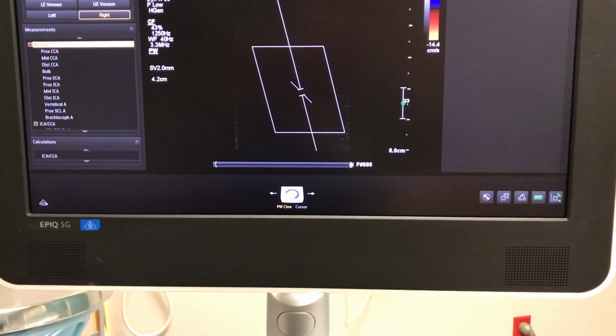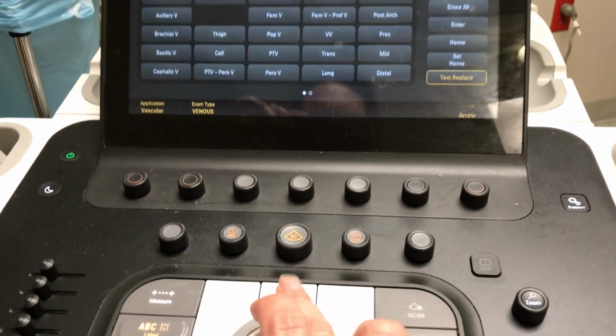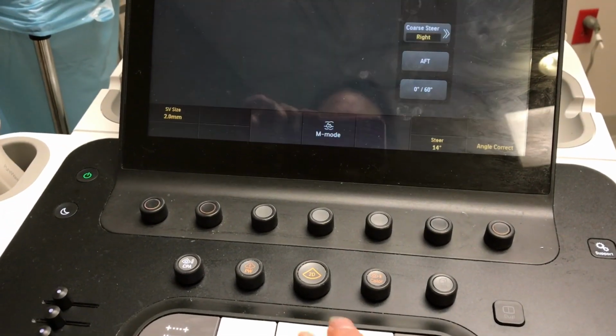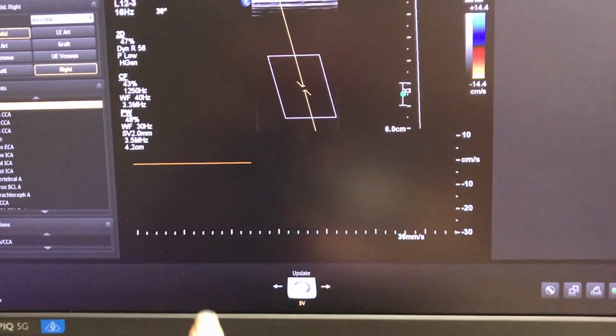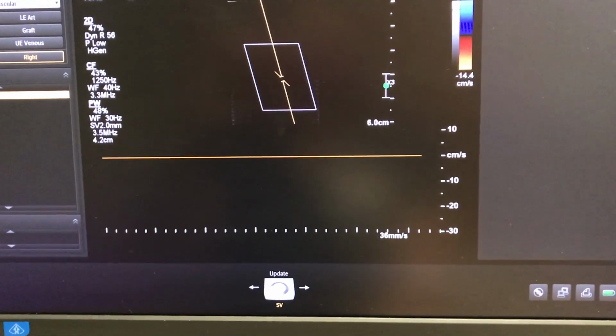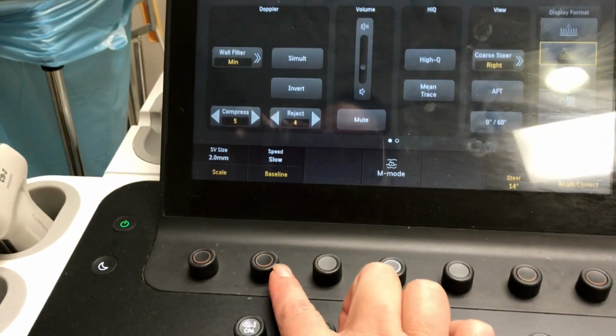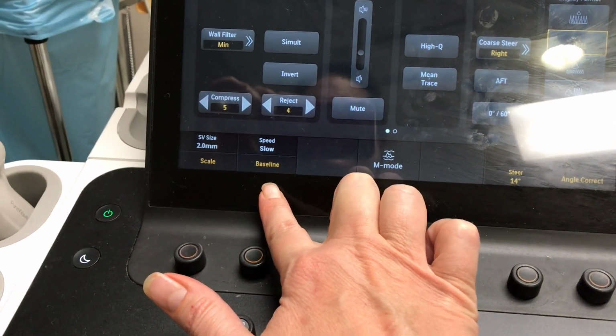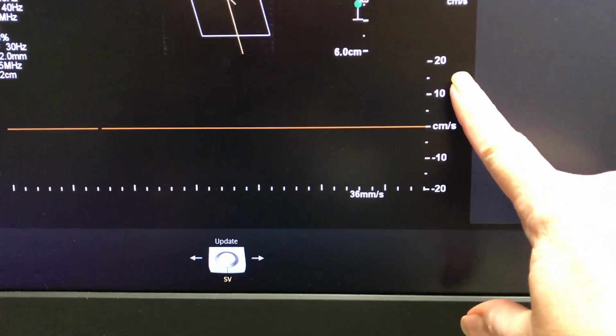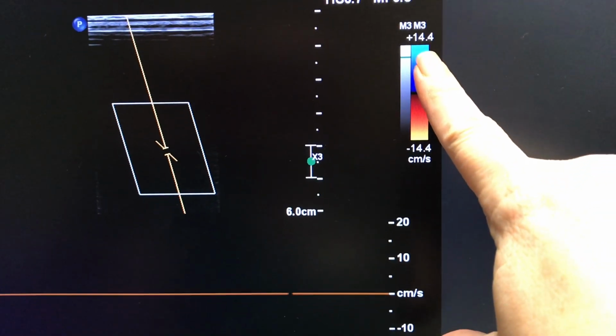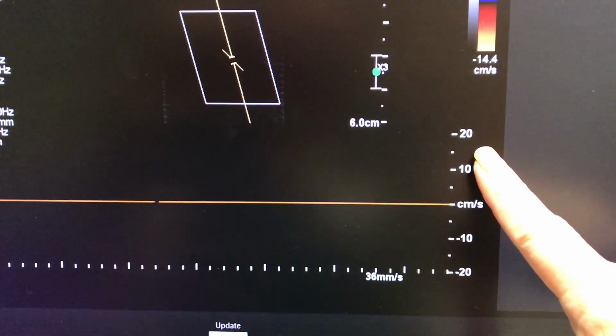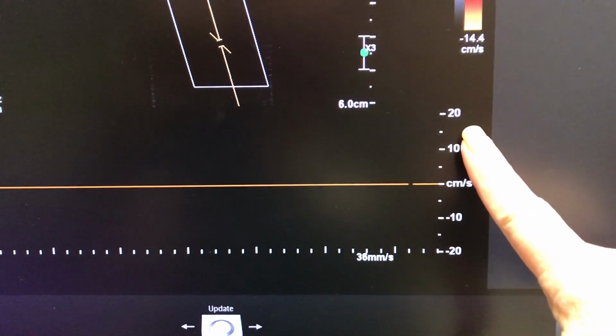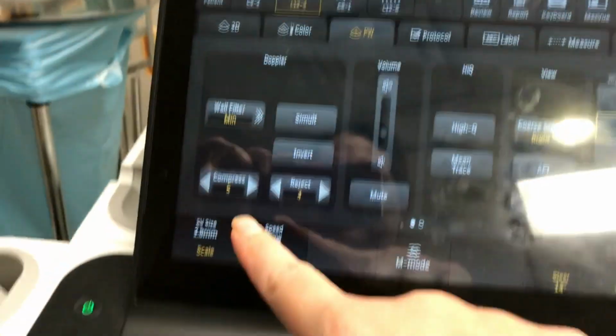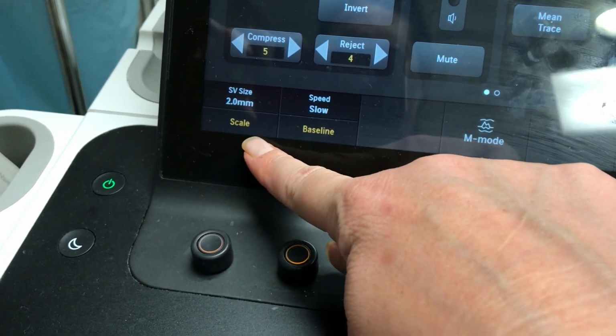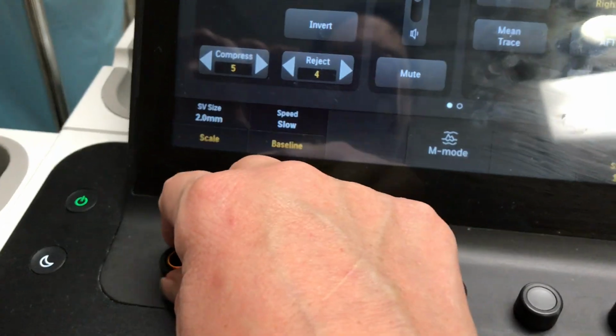Then to get your waveform, you hit the update button, and your scale is here. You can bring the baseline down. This is the button. This is indicating that it's baseline, and this is the button to turn. This is the scale your Doppler is set at. This is the scale that your color is set at. If this is a high flow vessel, you probably want to increase your scale, and that is right here. You can see the screen says scale, so that is indicating this is what this button's function is at this point in time.